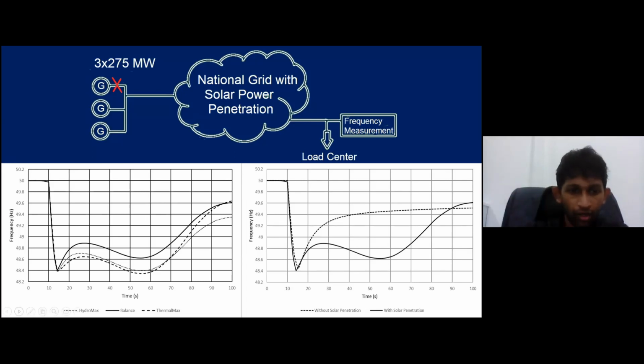But the problem in a hydro maximum scenario is that there is no governor response after a while. Most of the thermal power stations are working at base load. When I say most, I mean not by number, but by capacity. Let's forget about the gas and the small IPPs. The other power stations, as well as AES and the rest, together with Moratuwa, work at base load, or their governor setting is not that flexible.